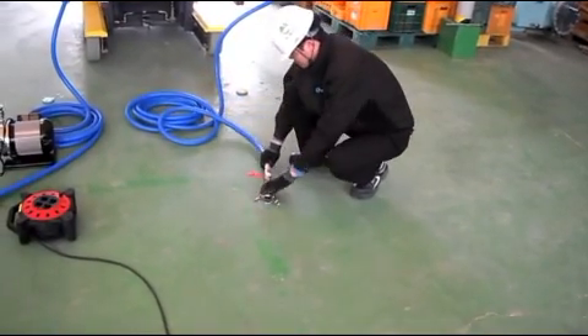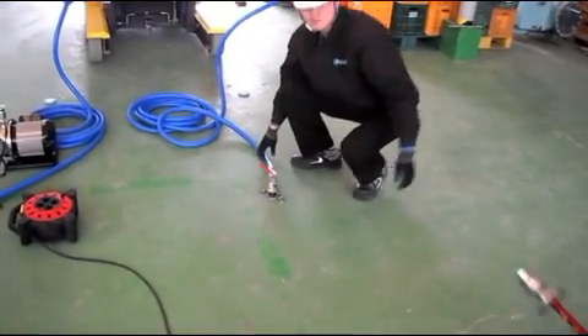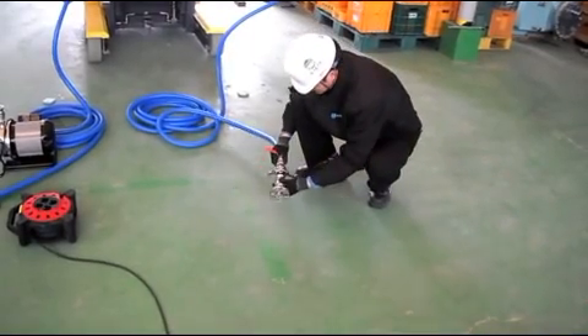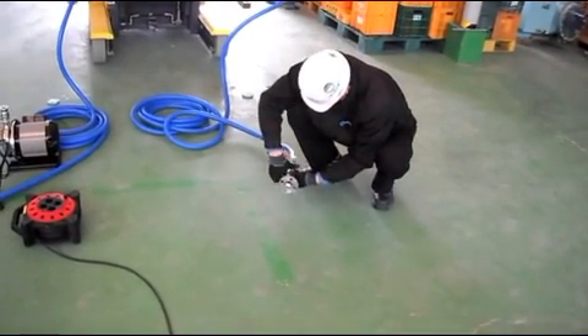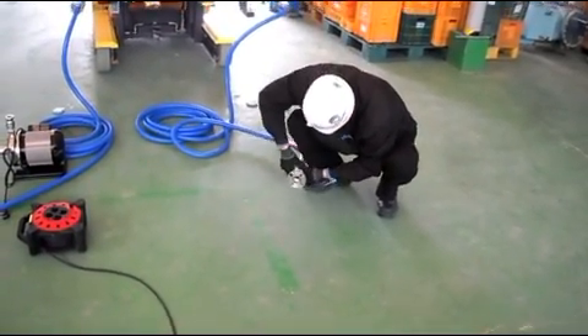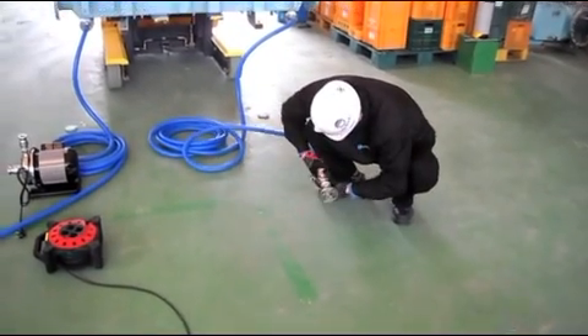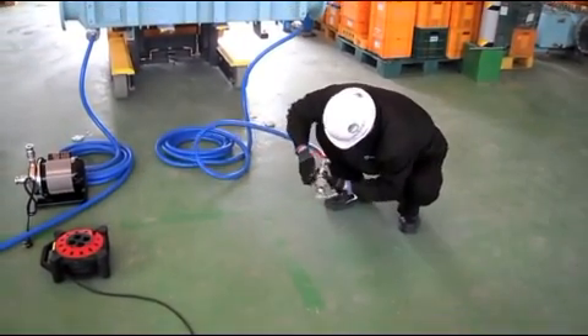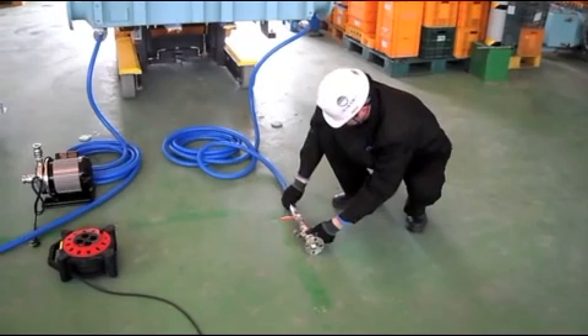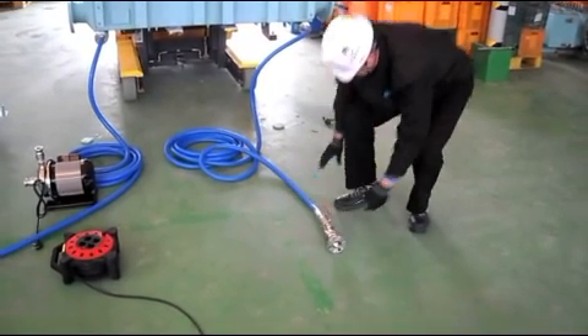6. Close valve V3 after flushing out fresh water for approximately 15 minutes. 7. Disassemble the pipe C1 and pipe C3. 8. Dispose of the collected cleaning agent according to the rules and regulations.